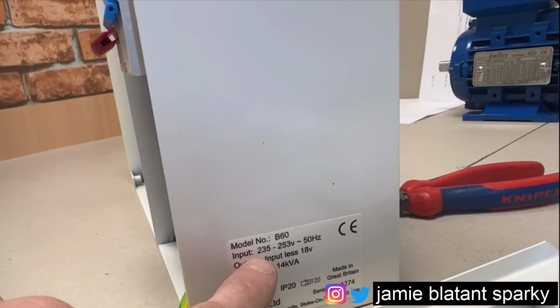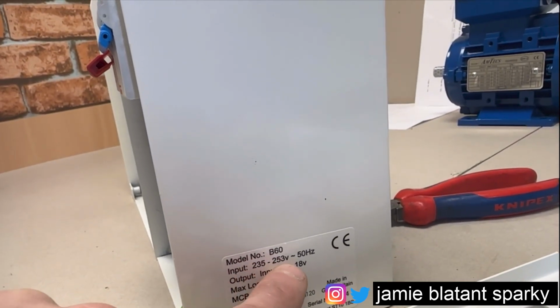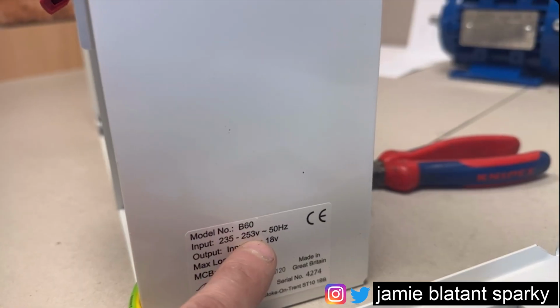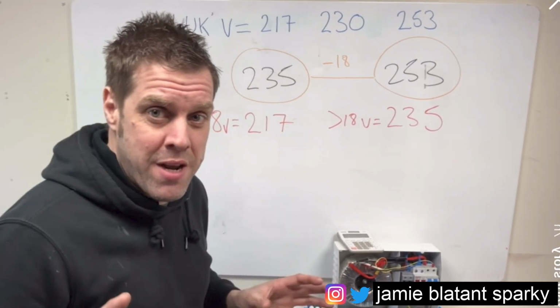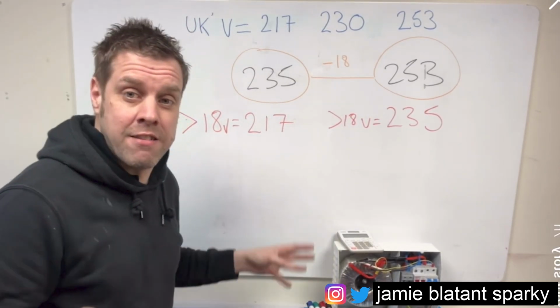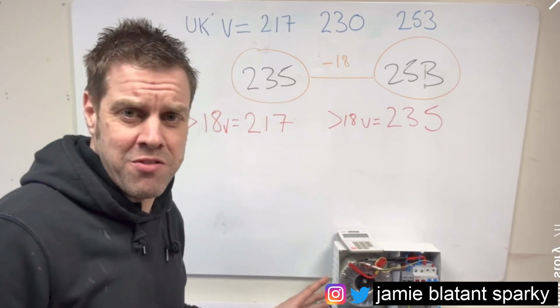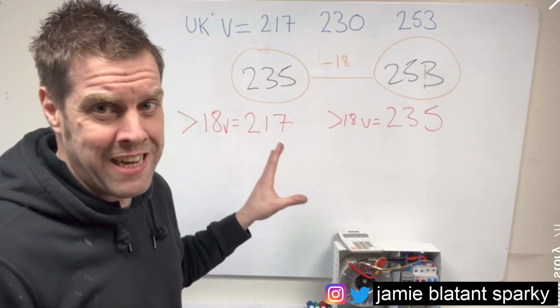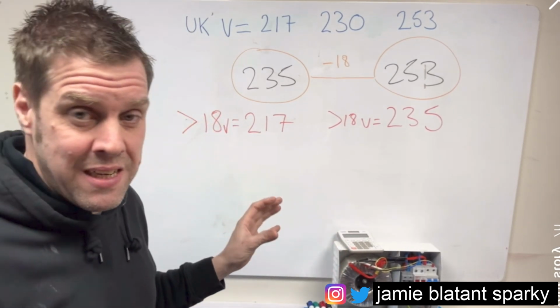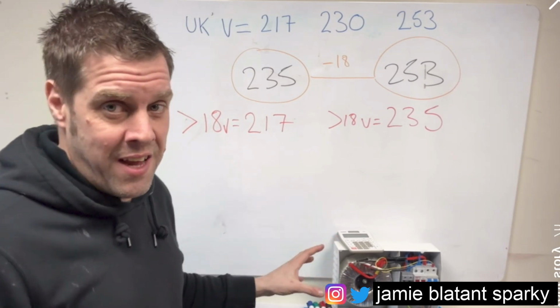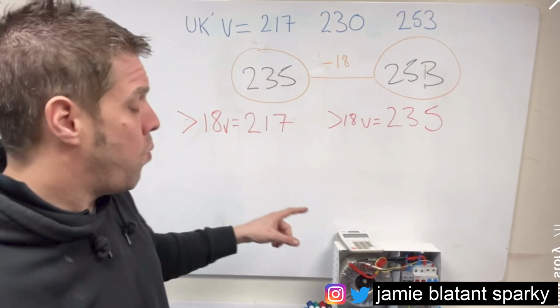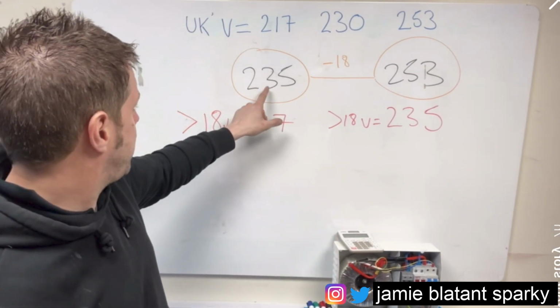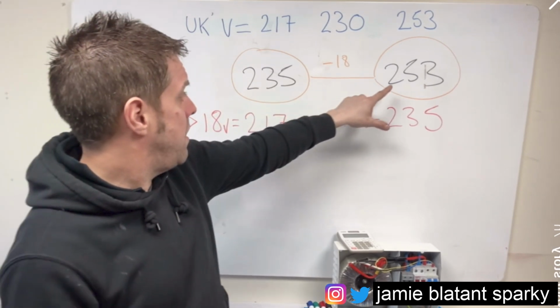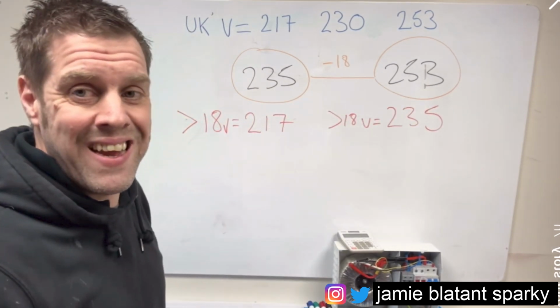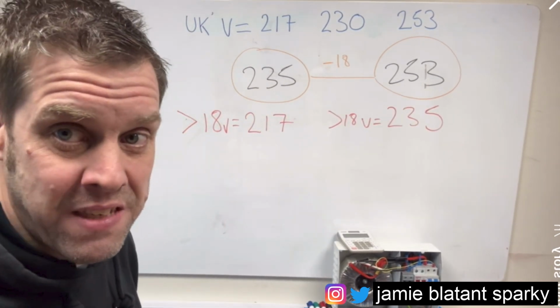The problem is the input of 235 to 253 - let's talk about that for a minute. Stop me if I'm wrong, let me know - this box of tricks does this. This voltage optimizer, as it's called, which has got no electronics in it, so I'm guessing because there's no electronics in there, it can only do what it says on the tin: whatever you put into it, between 235 and 253 volts, it reduces it by 18 volts.